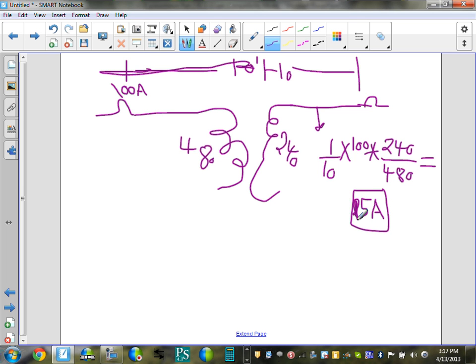5. The minimum conductor that you can tap there is 5. I know it's ridiculous, amp, but it will give you an idea. The minimum conductor that you can tap out of this transformer for 10 feet is 5. So obviously we don't put a 5 amp conductor. The minimum they put is number 12. Because the current, this 100 here on the primary side, when you move it to the secondary, it will be seen as half, right? Because of the voltage ratio.